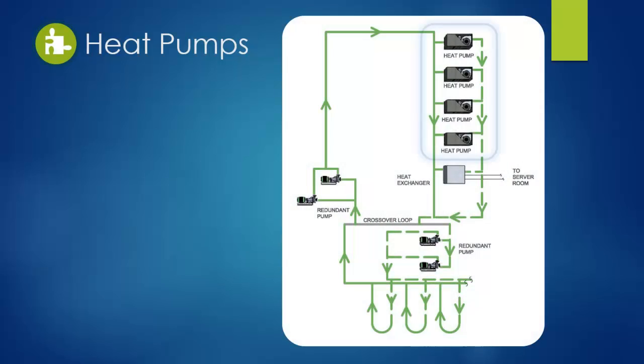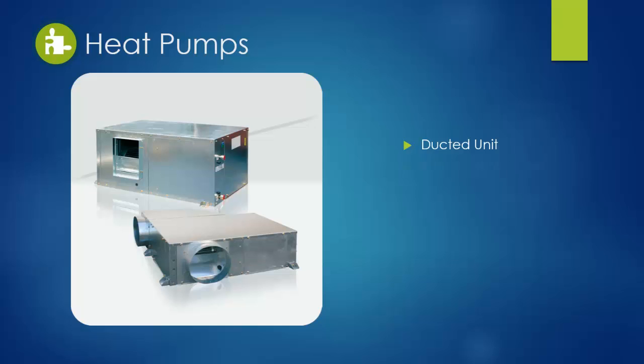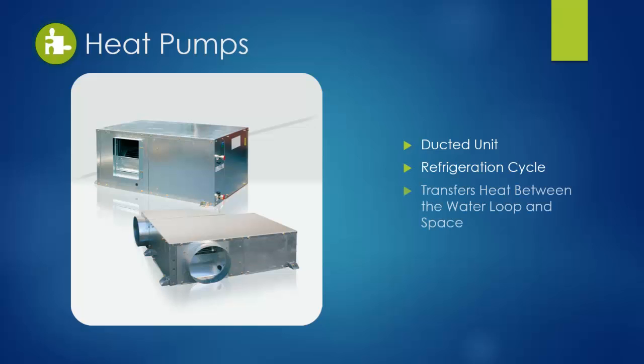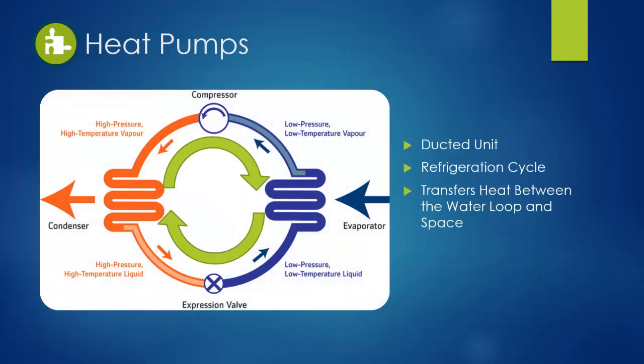Component 3 is the heat pumps. The heat pumps will be ducted units located at the zone level that utilize a refrigeration cycle to transfer heat between the water loop and the space.